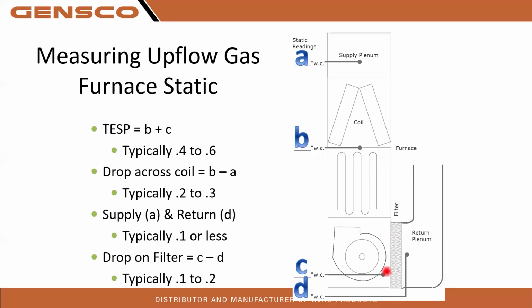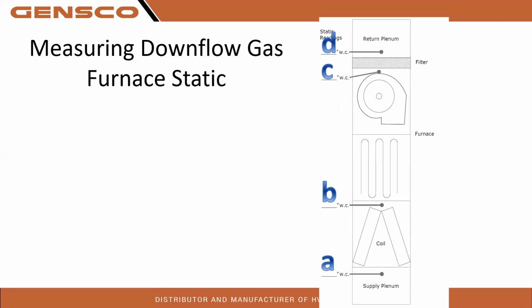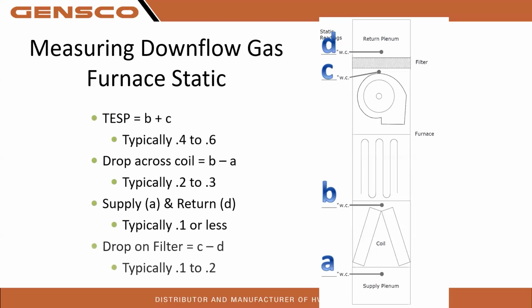Drop on filter C to D, typically 0.1 to 0.2. And I'll show you a chart on how that affects your airflow through the filter also. Measuring downflow gas furnace. So in downflow, it's pretty much the same thing as the upflow.